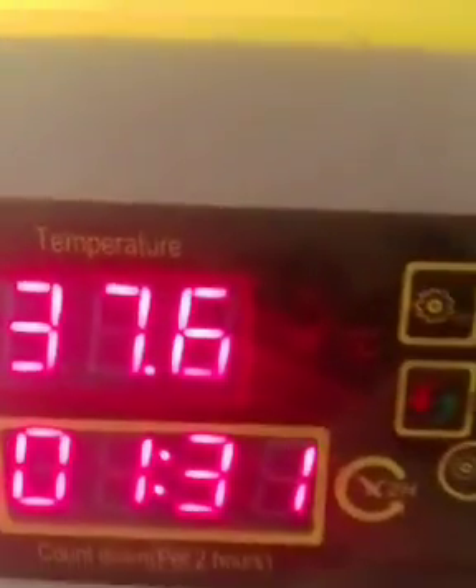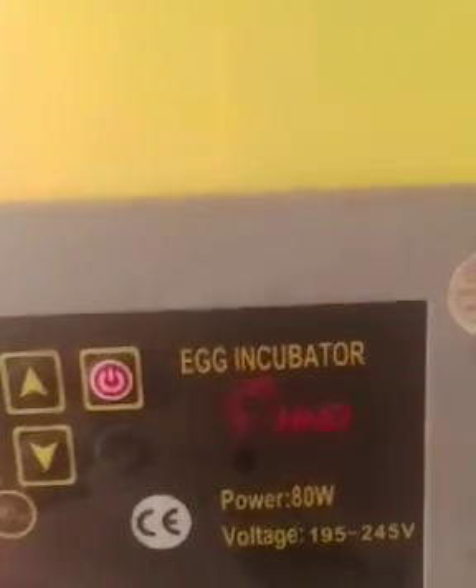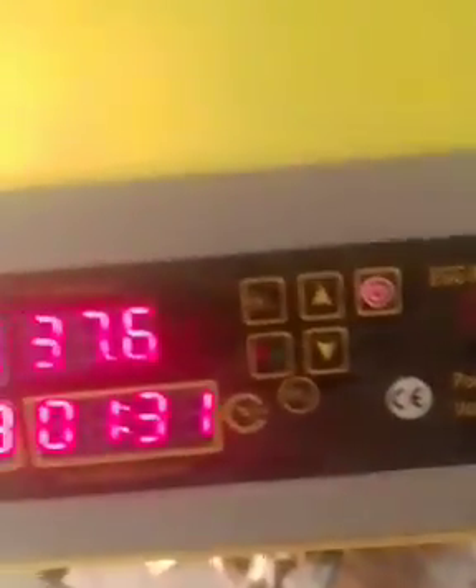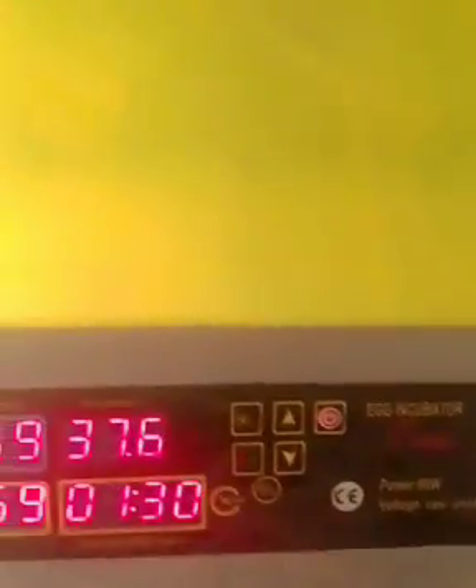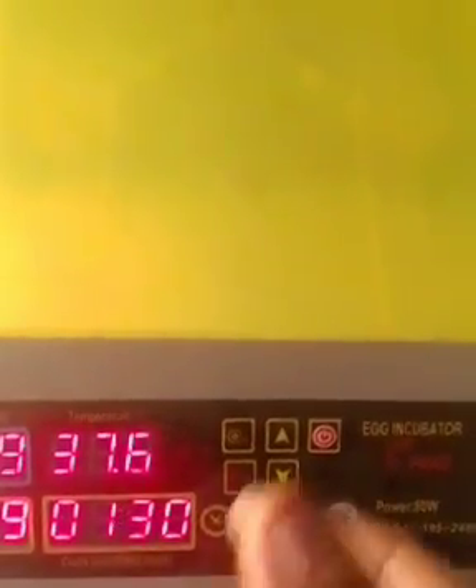You can see the power unit. One good thing about this particular incubator is that it can use both electricity and even a battery. A motor battery can control it. You can see this is for direct current, and this is for battery. You can see the source for the battery. You can make use of direct current, or alternating current, which is the electricity or solar. So if you connect a motor battery to this now, it will work very well. And it can carry it for days, depending on the capacity or the amperage of the battery you are using. Now, let's open the incubator so that you see.